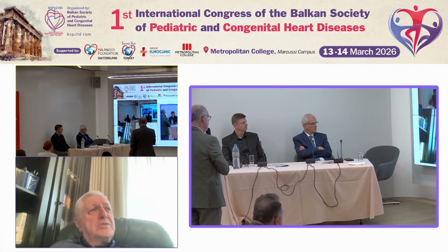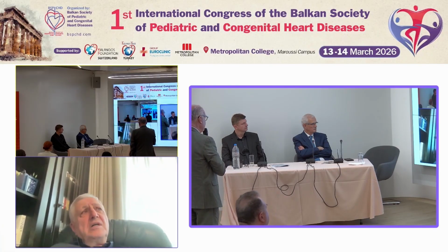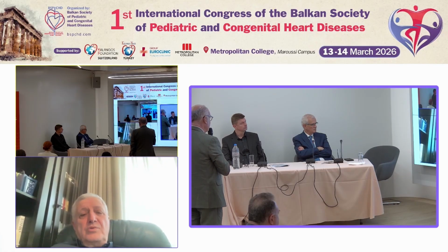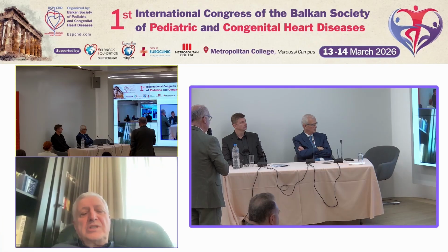Yeah, actually, it is also a good question, especially in patients with altered geometry of the ventricle. You should be very careful because these devices are made mostly for normal ventricles. Even if you put the device in the correct position, migration can happen.